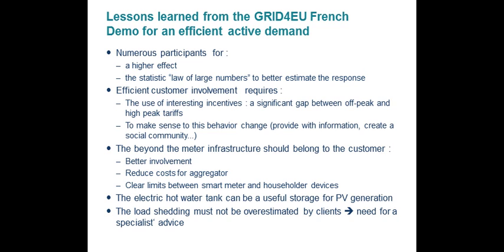Water heater remote control was set up in the mid-90s to provide load during the night for French nuclear power stations. Now it's an opportunity for us, because we use the water heaters and their remote control to do active demand management, and in the GRID4EU project, to bring more load onto the grid during the afternoon to absorb PV generation. The infrastructure for that is already in place.